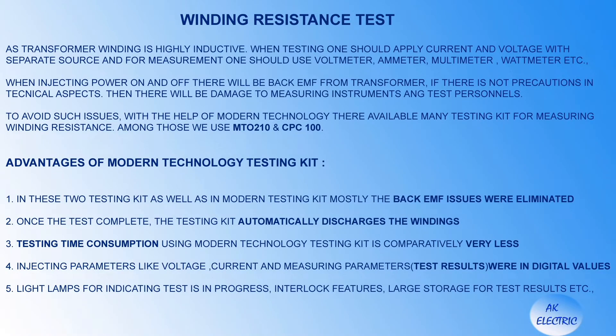As transformer winding is highly inductive, when testing one should apply current and voltage with a separate source, and for measurement one should use voltmeter, ammeter, multimeter, wattmeter, etc. When switching injecting power on and off, there will be back EMF from the transformer. If there are no precautions in technical aspects, there will be damage to measuring instruments and test personnel.